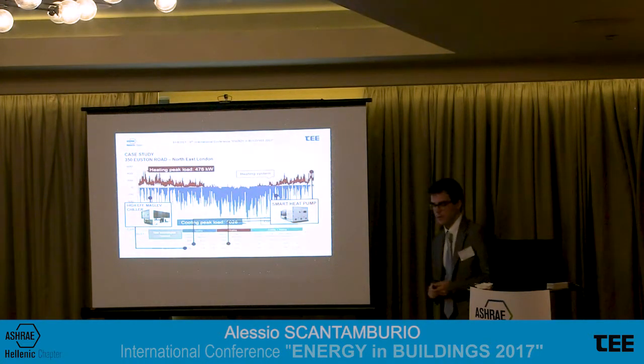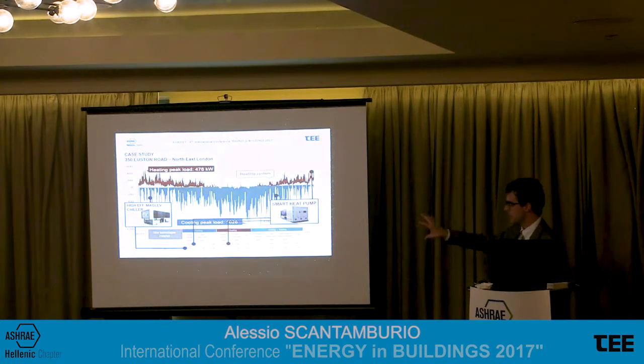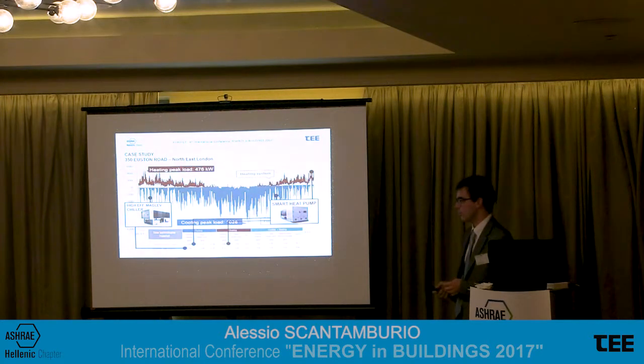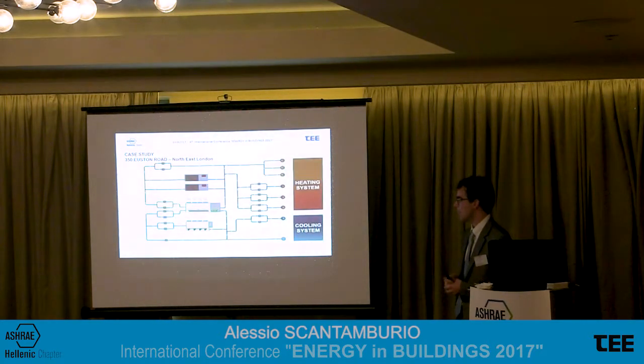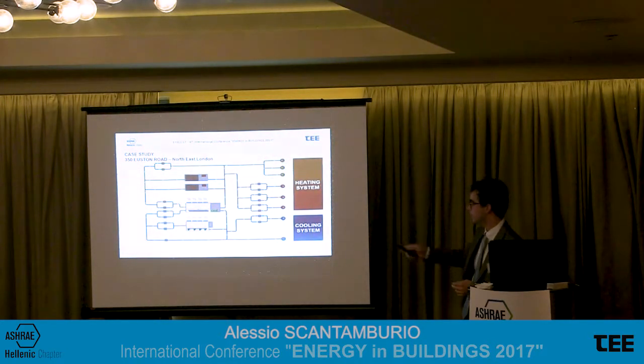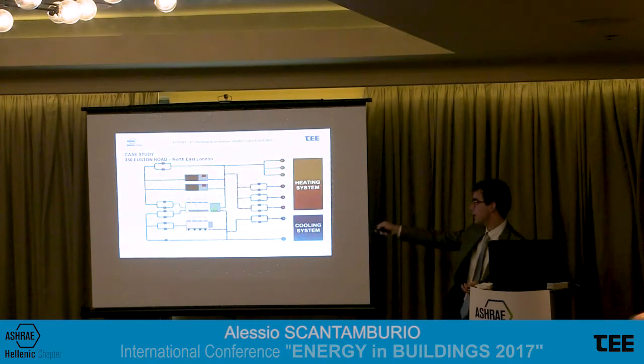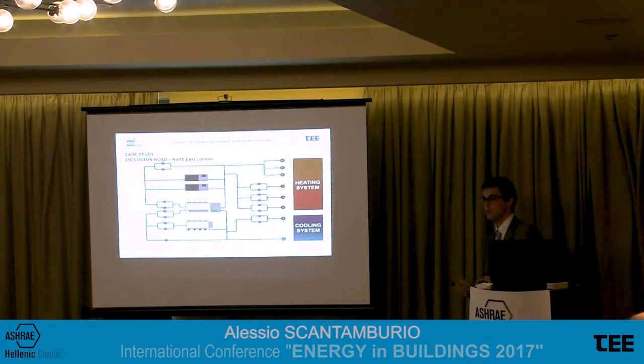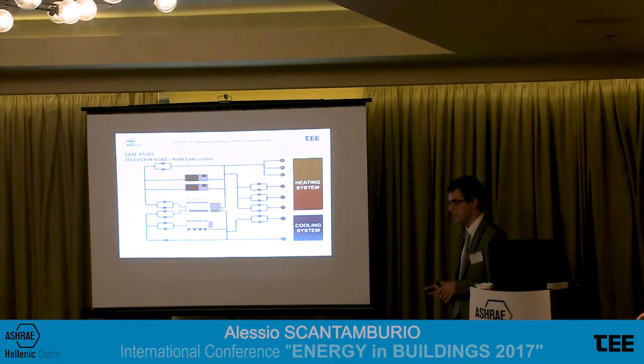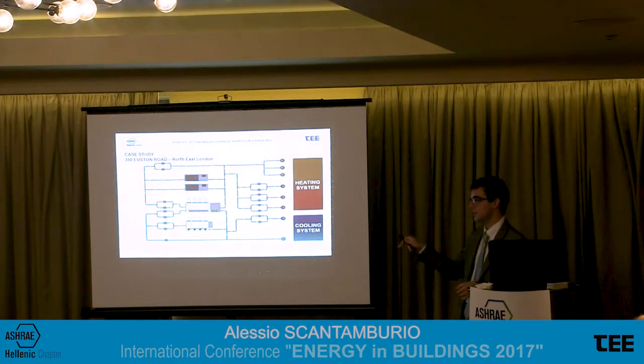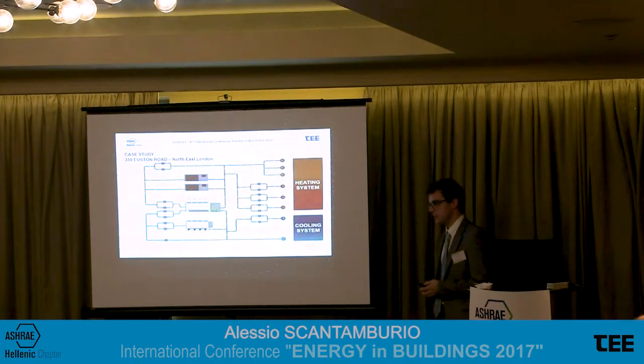We carried out our energy analysis considering the efficiency of this combination of plant. And this is just a general, very simple view of the plant. We have, of course, the 4-pipe unit connected both to the heating system and to the cooling system. The chiller is connected only to the cooling system, and then the tenants decided to keep the gas boilers as a backup, because the dismantling cost was really high and they were relatively new. But as we later see in the results, they mostly never use it.